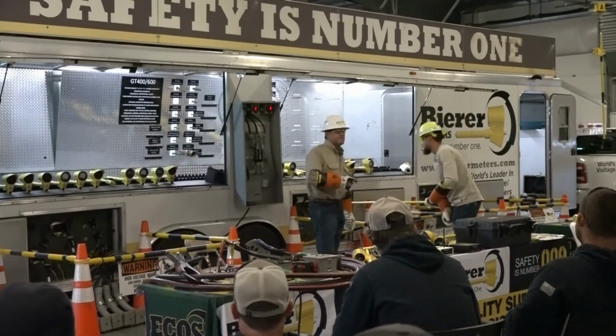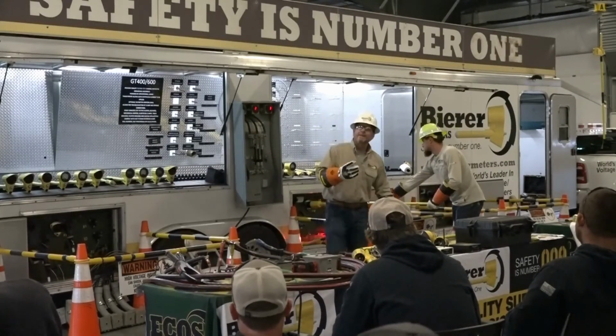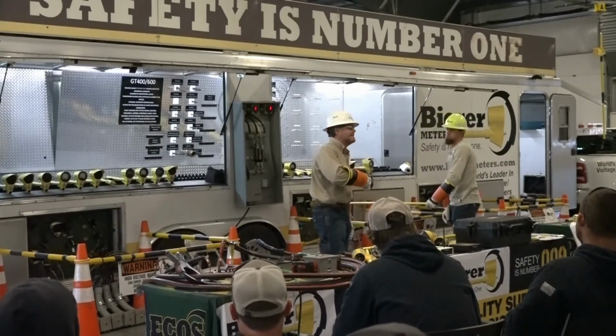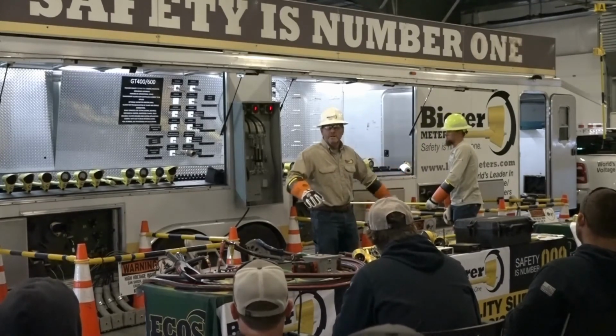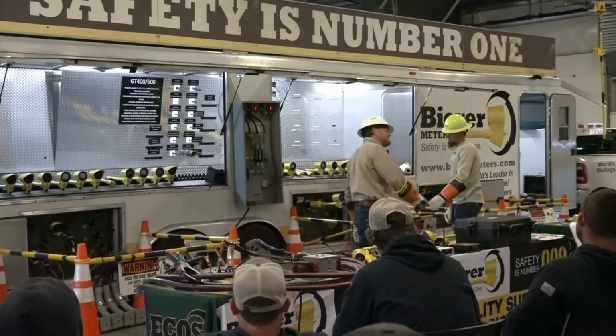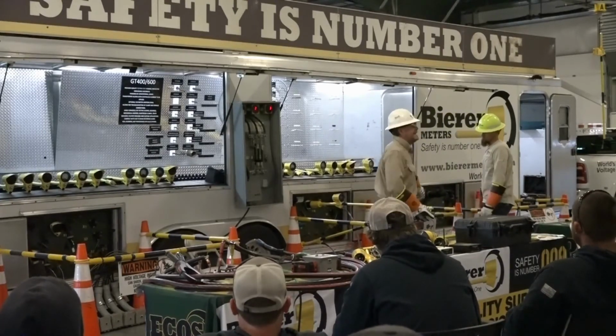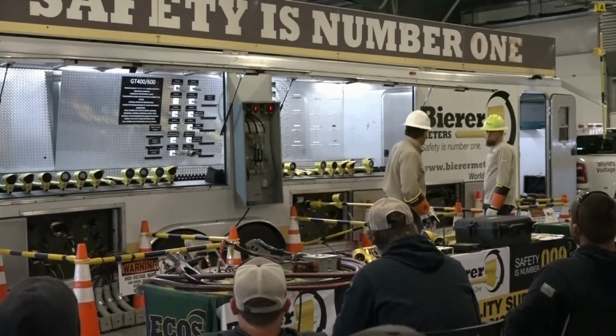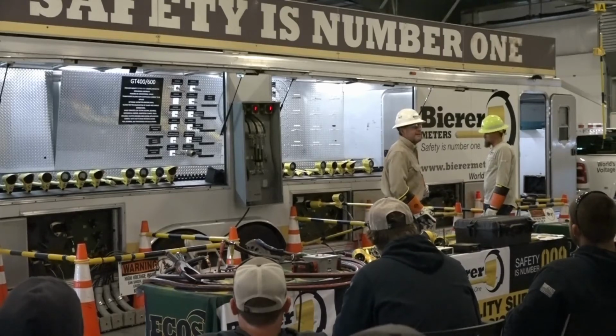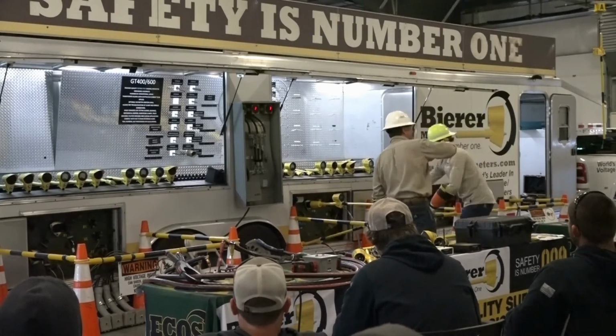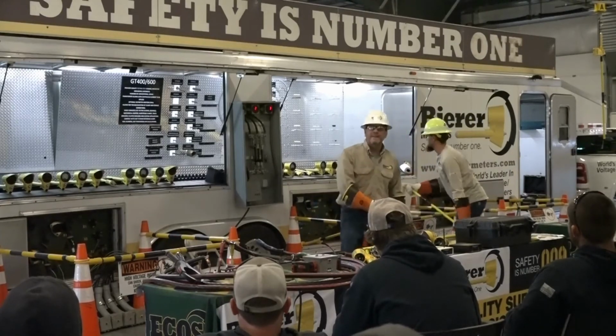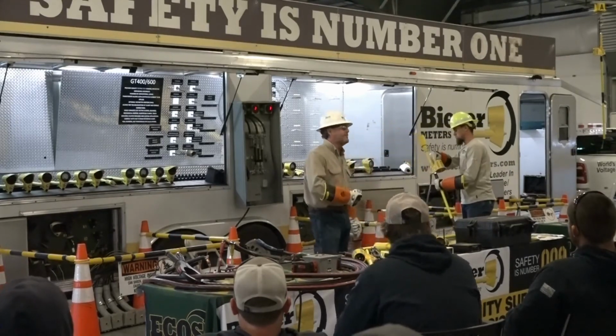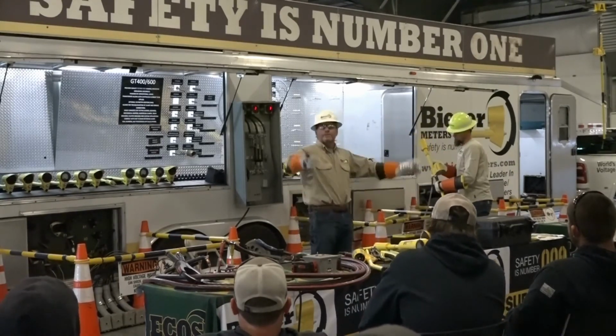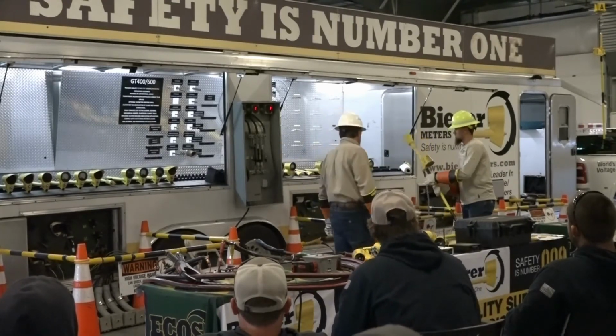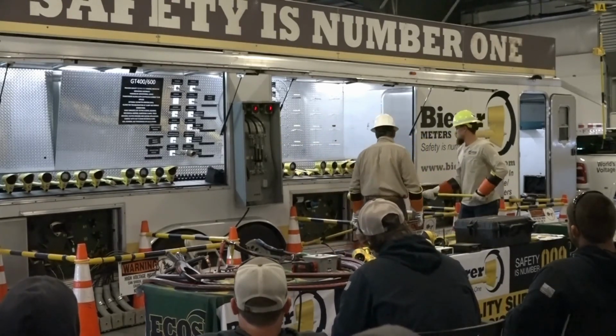1. So the tool, Dylan's got it on 2 kV. The tool's telling Dylan, and all of our tools speak to you. Once you learn how these work, the tool's telling Dylan that he's got it on overload, that he's on secondary. So Dylan's going to take the tool back off, take the switch plate, and go to 25 kV. He's going to tell the tool that we're working this high line, high voltage, not doing capacitive test points. All right, go ahead buddy.